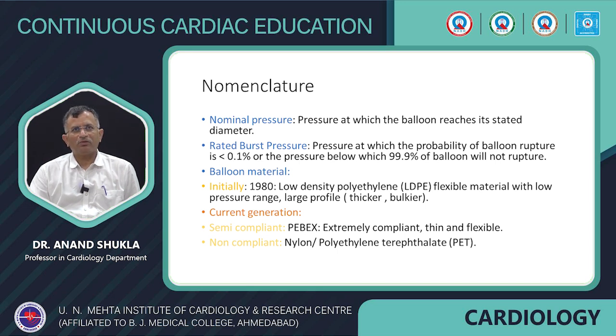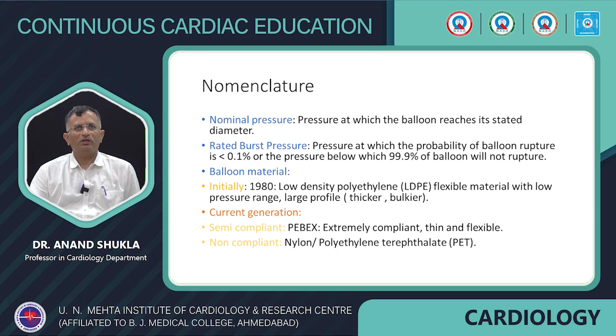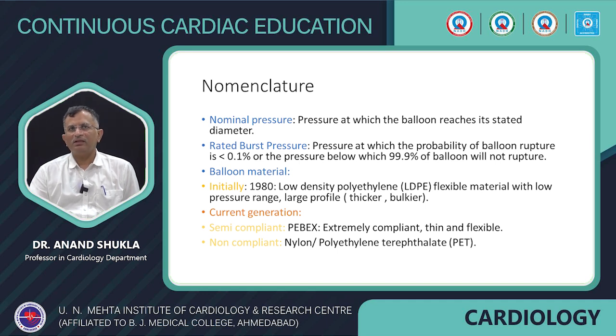There are certain nomenclatures: nominal pressure is the pressure at which the balloon reaches its stated diameter. Rated burst pressure (RBP) is the pressure at which the probability of balloon rupture is less than 0.1%, or the pressure below which 99.9% of similar balloons will not rupture.